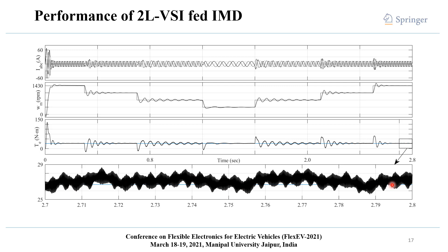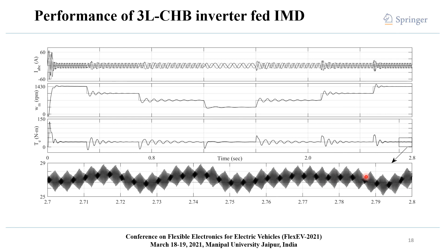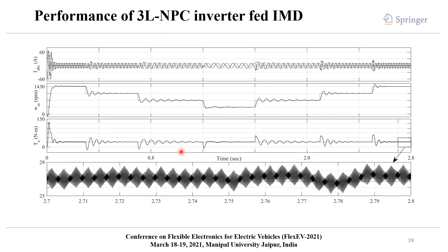This is the zoomed view of the rated torque for the 2-level voltage source inverter fed induction motor drive. This is the performance with the 3-level cascaded H-bridge inverter. Here you can clearly see that there is a reduction in torque ripple with the 3-level CHB inverter as compared to the 2-level voltage source inverter, and this is the performance with the 3-level NPC inverter fed induction drive. Here again there is a reduction in torque ripple as compared to the 2-level voltage source inverter. This is the comparison of obtained parameters.